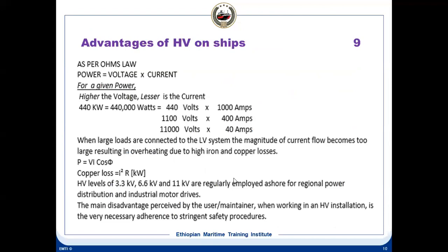So let's start by seeing this. What are the advantages of high voltage on ships? See, generally, power is voltage into current. In the case of a DC circuit, voltage multiplied by current is your power. But in an AC circuit, it is voltage multiplied by current multiplied by the power factor, is it? So why is there no power factor in a DC circuit? In a DC circuit, power is voltage into current, but in an AC circuit, it is voltage multiplied by current into cos phi.